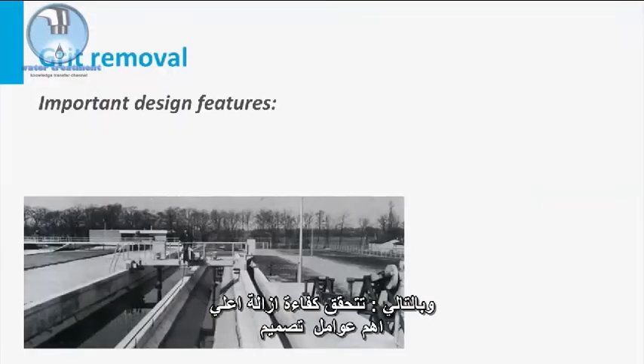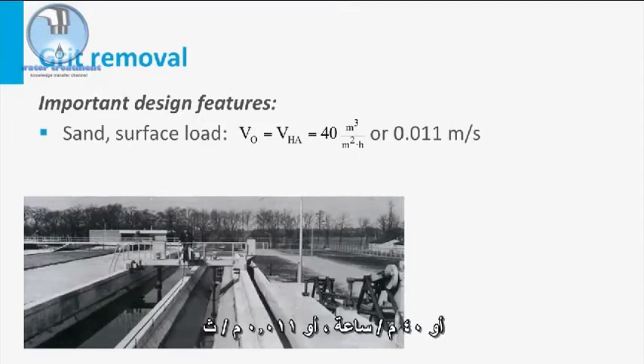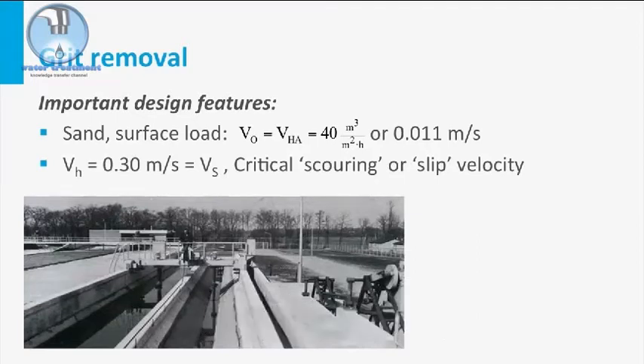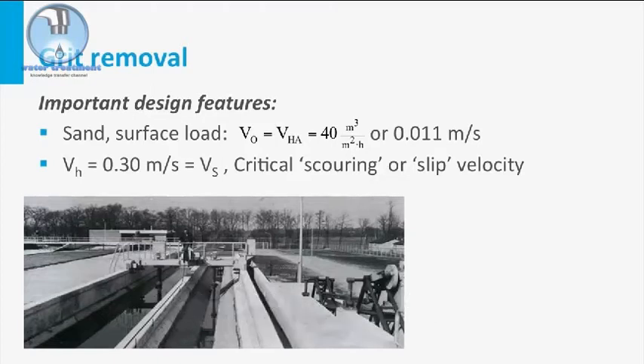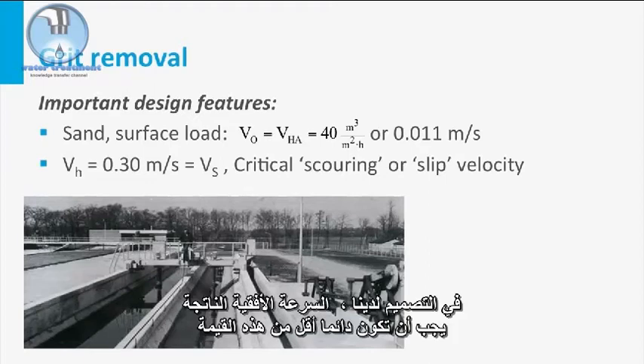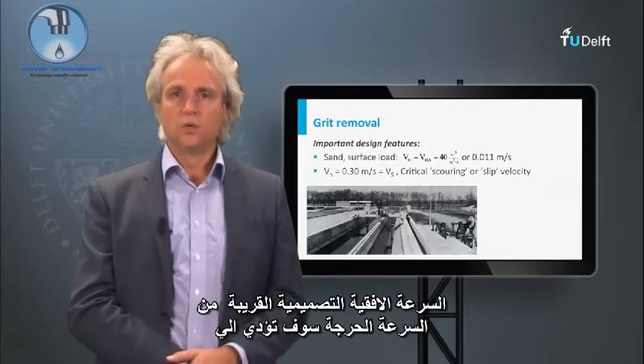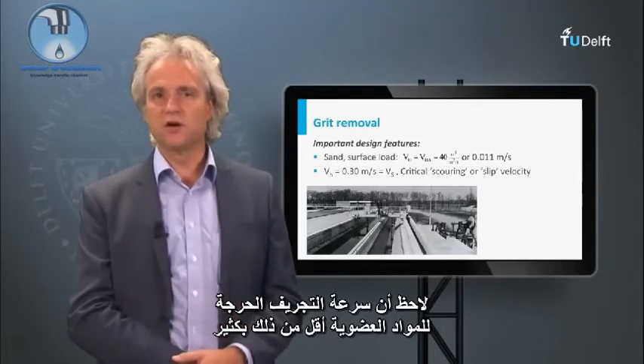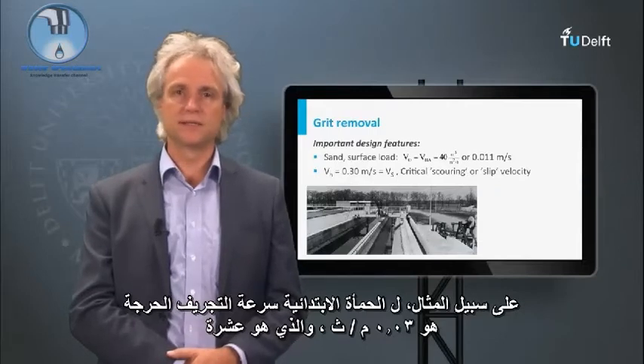The most important design features of a rectangular grit chamber are: first, the maximum hydraulic surface load, or Hazen velocity, should be below 40 cubic meters per square meter per hour, or 40 meters per hour, or 0.011 meters per second. Second, the critical horizontal velocity that may lift the sand from the bottom is 0.3 meters per second — this is called the critical scouring velocity or slip velocity. The resulting horizontal velocity must always be below this value. A design horizontal velocity close to the critical velocity will result in an excellent separation of sand particles from the organic fraction. Note that the critical scouring velocity of organic material is much lower — for primary sludge, it is 0.03 meters per second, which is 10 times less.